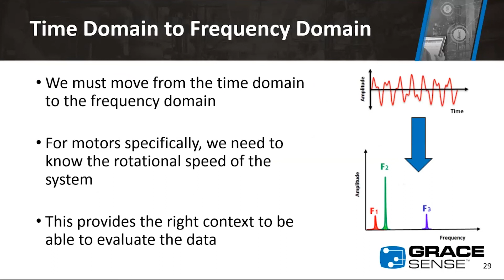If we move from the time domain to the frequency domain, we're just going to walk through what happens in a vibration analysis for a motor. The first step is that we take data that we capture over time and bring it into a form where we can look at it in regards to the rotational speed of the motor. This provides the right context to be able to analyze it. So you have your machine of interest that one of our vibration temperature nodes would be on. Then we grab the analog voltage output, digitize it, and send that to the processor to perform an FFT analysis. FFT stands for fast Fourier transform, and it's what takes us from the time domain into the frequency domain.